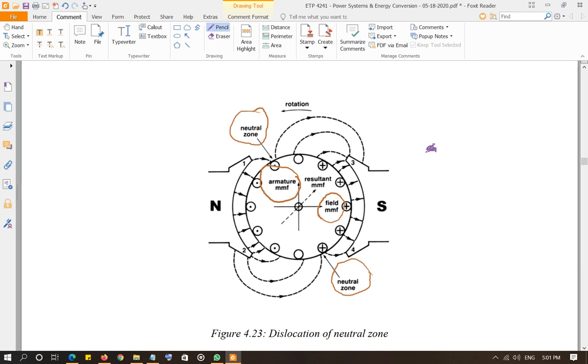When this magnetic field interacts with the magnetic field of the permanent magnet, the magnetic pattern on the armature is shifted, which shifts the neutral zone, which creates sparking at the brushes. Your brushes are no longer located at the neutral zone, hence they will be touching commutator segments that are shorting out a coil that now has induced voltage. So this whole story is what armature reaction is.